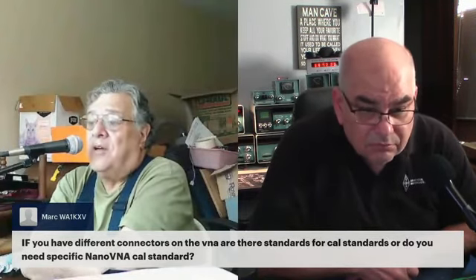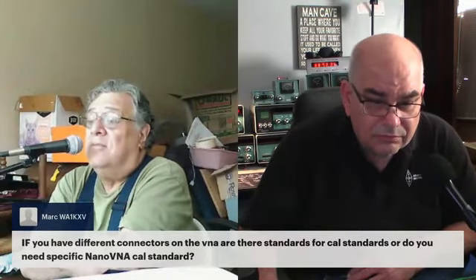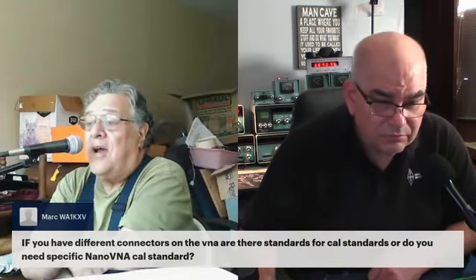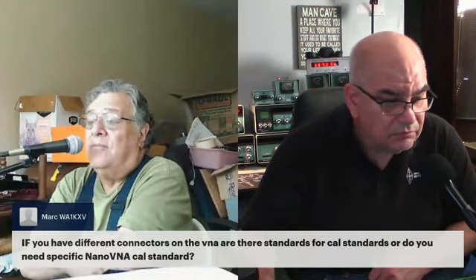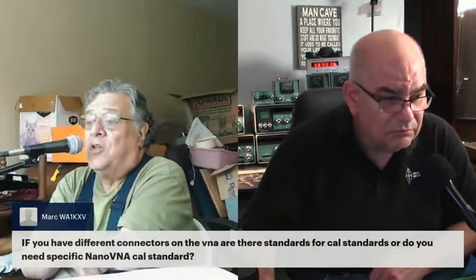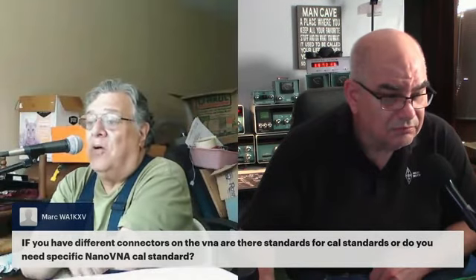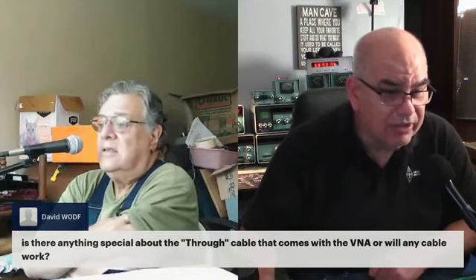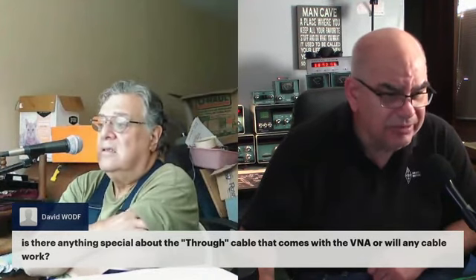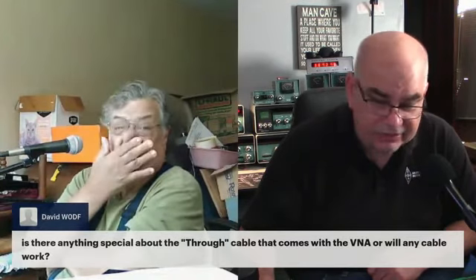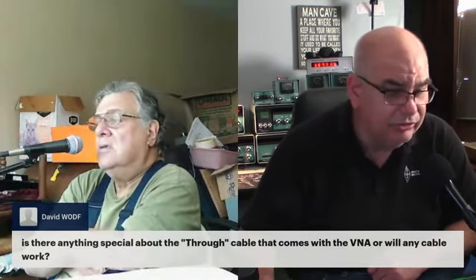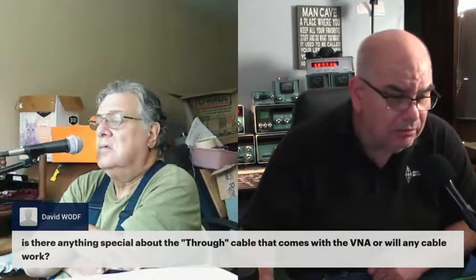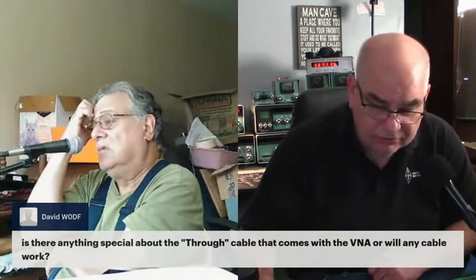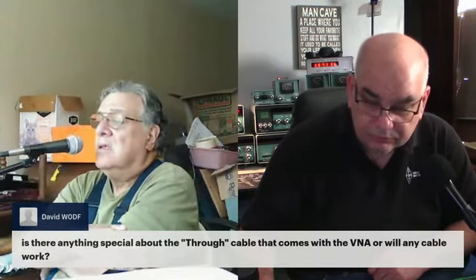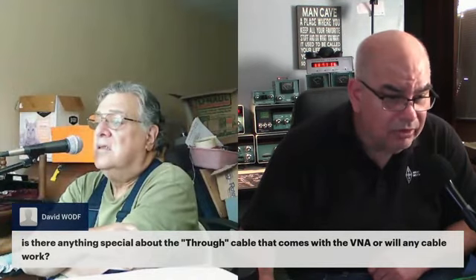But if you were measuring up at 500 megahertz or 900 megahertz up in the higher ranges, it might matter more. But wherever you do the calibration with the short open load, that becomes the reference plane for the measurement that you're going to do. Yeah, and those cables that come with it, you want to do a calibration when you're using those cables. As with my SO239 type, you do the calibration with that, and when you do the through, I just put in a PL to PL male adapter, and that way I can do my through, and I'm relatively good.